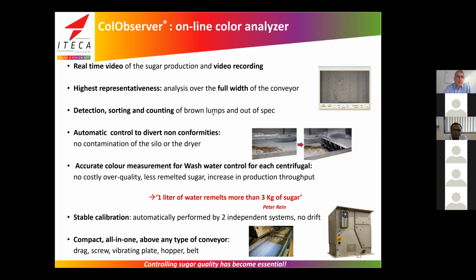After installation, you have to follow the system, because this is an online system, not a fire and forget system. When we put in an online system, we have to follow it, meaning check if everything is okay, if the air conditioning system is working well. We have a Peltier system here, which is totally waterproof, but you have to take care that the fan of the system is running well. If not, you may have some drift in the measurement because the temperature inside is not correct.